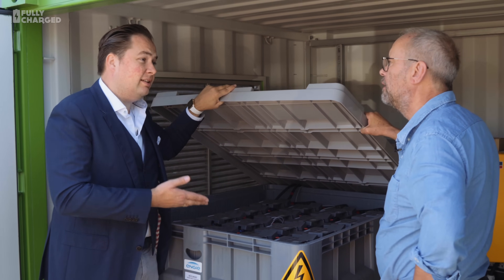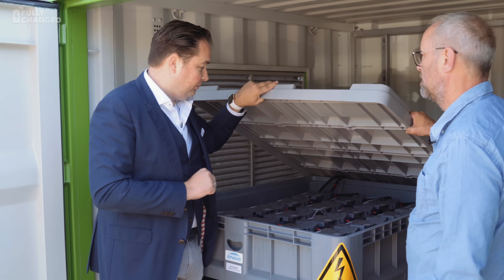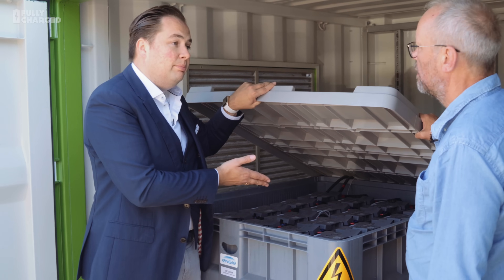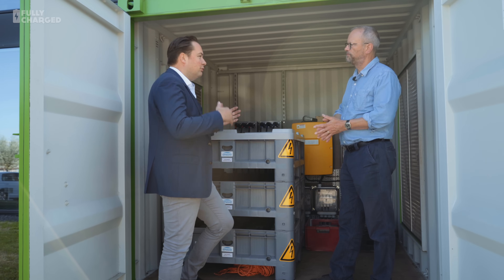They're probably not good enough to use in a vehicle anymore, but they have more or less 80% of their capacity still, which for us is perfect. And when the state of charge of a certain box drops below a certain level, we just switch the box. Because this is very cheap storage. The demand on it is constant — when you're charging it's regulated, and when discharging it's the same — there's no sudden massive demand. You can't do frequency containment or control, but you can do perfect storage for buildings like this. This container is more or less 60 kilowatt hours.